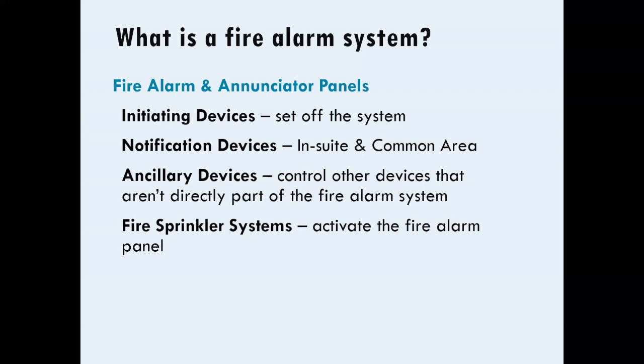In this list that I've shown here, the 5 items listed immediately under fire alarm panel or fire alarm and annunciator panels all represent devices or systems that are interconnected to the fire alarm control panel itself and will either initiate an alarm on the panel or will activate the signal devices upon initiation of the alarm. So the devices include 3 different headings: initiating devices, which include heat and smoke detectors, as well as pull stations; notification devices such as bells, horns, speakers; and ancillary devices. These are devices that are attached to the fire alarm system, but are not part of the fire alarm system.